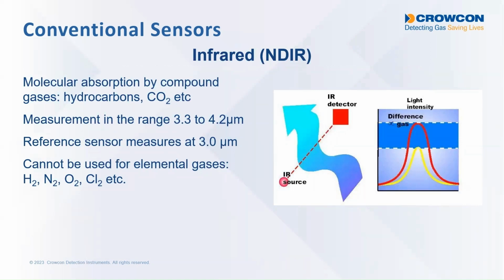Because of the drawbacks of the pellistor, the limitations, infrared sensing technology was developed during the 80s and 90s, and the first instruments came to market in the 1990s, and it uses an optical method of detecting the presence of hydrocarbon gases. So this technique is only able to detect gas molecules with dissimilar atoms. So things like hydrocarbons have hydrogen and carbon atoms. Carbon dioxide has carbon and oxygen atoms. It's not able to detect elemental gases such as hydrogen or nitrogen.